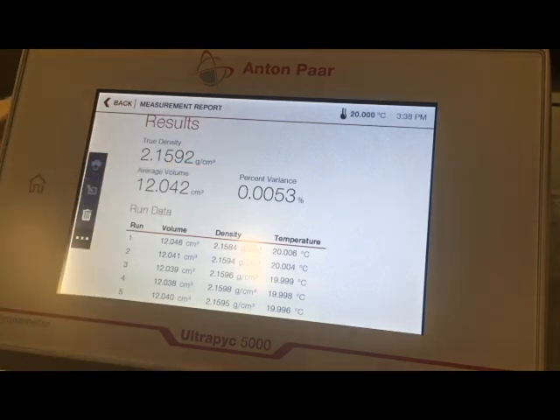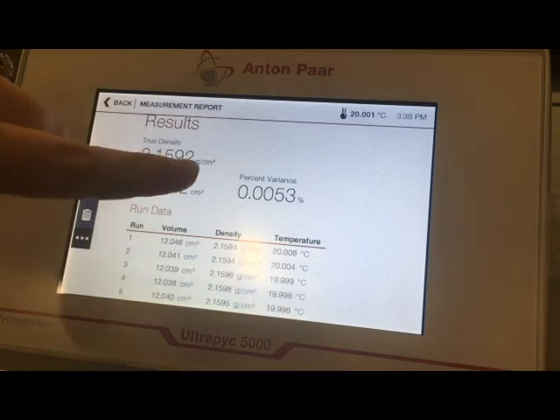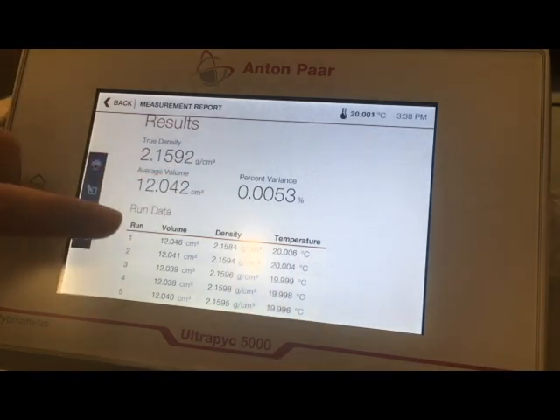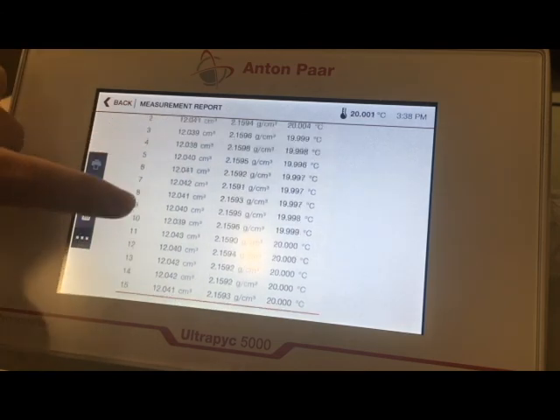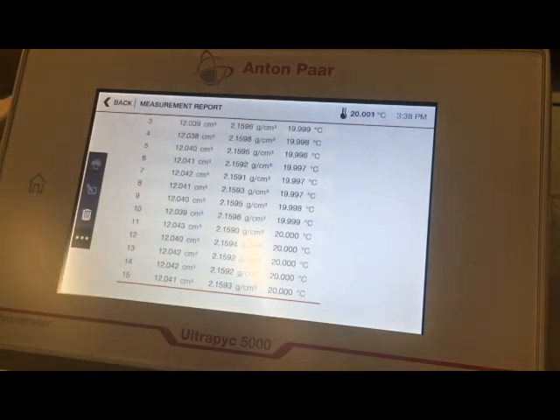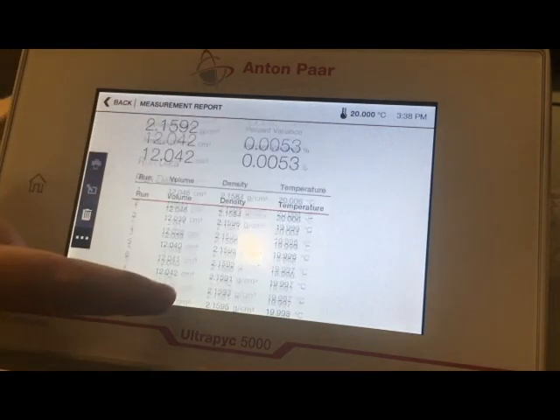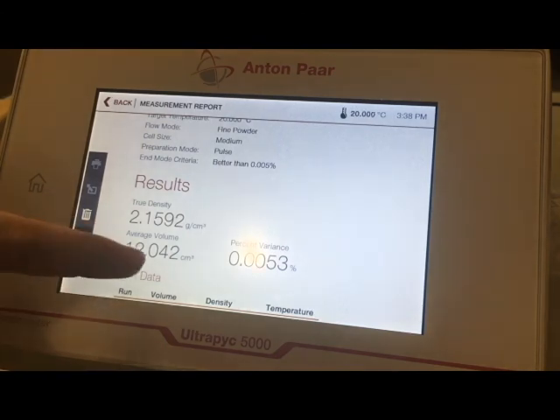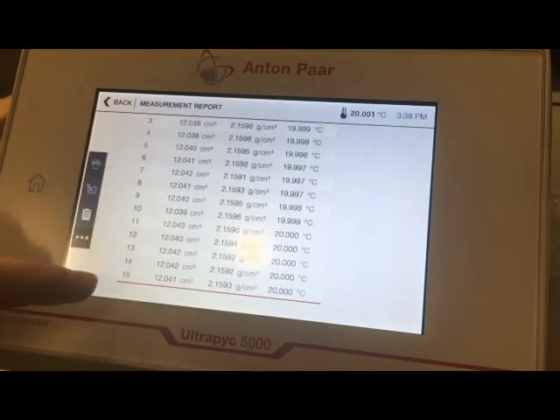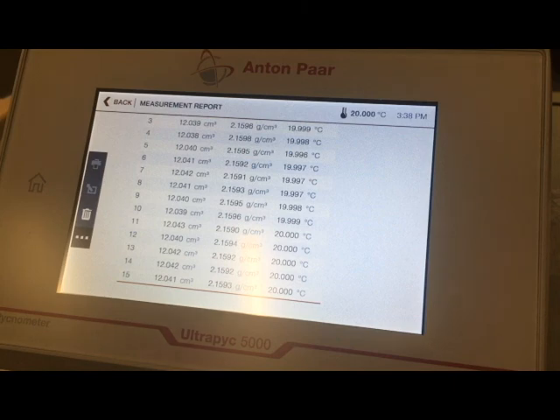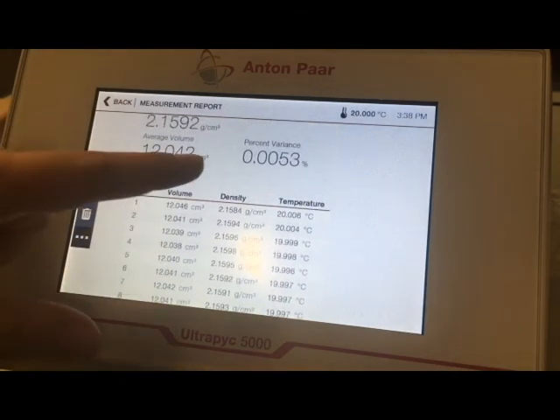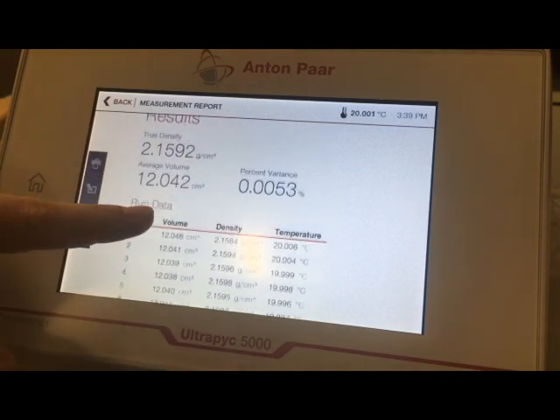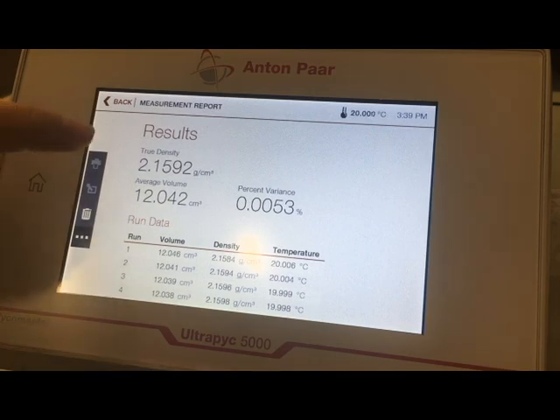You can see my percent variance, which I set to be 0.005. You can see my actual error is 0.0053%. And you can see all of the tests that it ran. This one actually took 15 tests to run. If I had set the value to be a little bit higher, based on the fact that I have pretty close to 0.005% variance, I am going to guess that it would not have taken many more tests for me to get to a true 0.005. So this test did time out because it would have taken more than my full 15 tests to get my true percent variance here, but we did get really low error and a really awesome value for my density here.